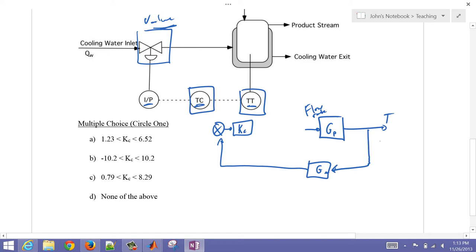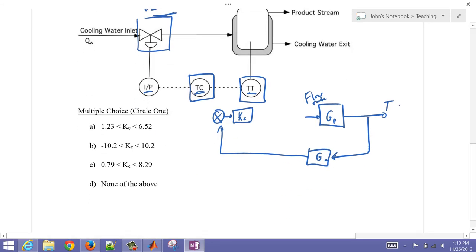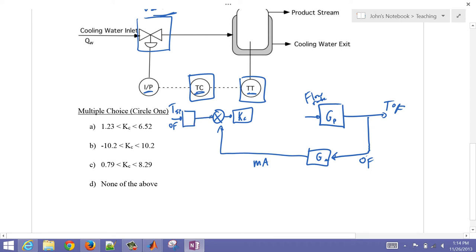What kind of units are those — this temperature right here? That's degrees Fahrenheit. This is also degrees Fahrenheit. We're splitting it off. And what is this measurement here after we've converted it? This is milliamps. And then we have a set point — what are the units of that? That's degrees Fahrenheit. We want to convert that into milliamps so we can compare milliamp to milliamp. How do we convert from degrees Fahrenheit into milliamps?